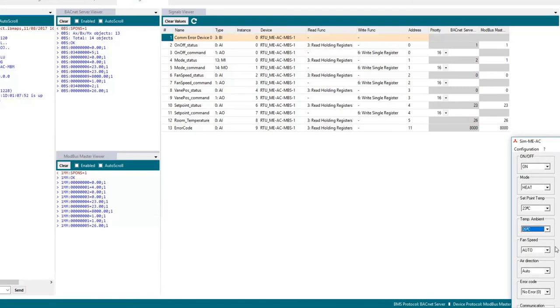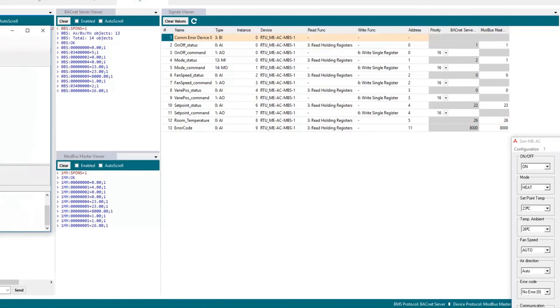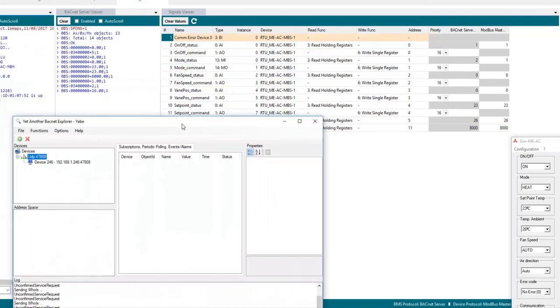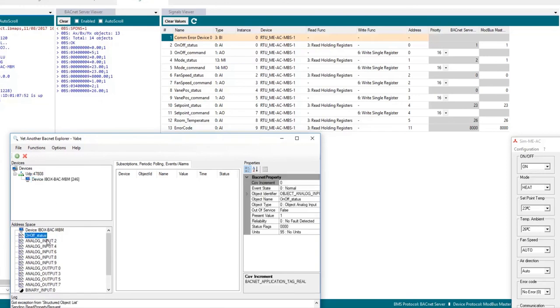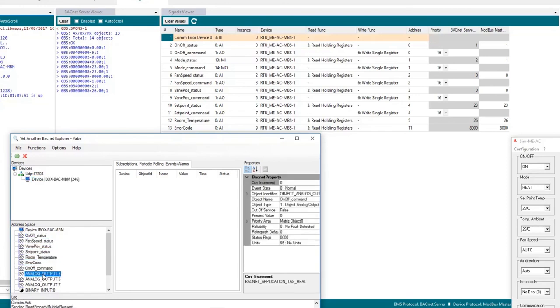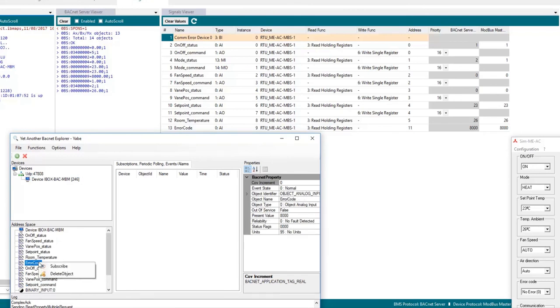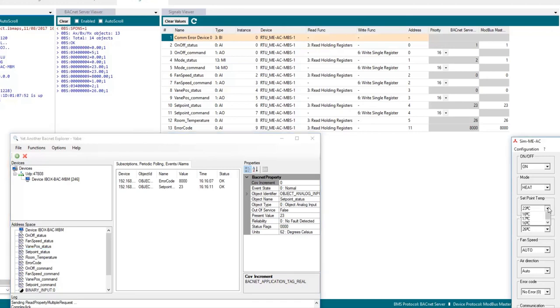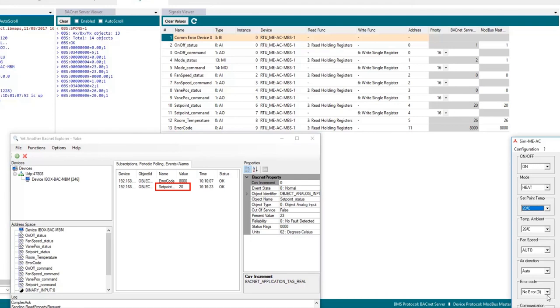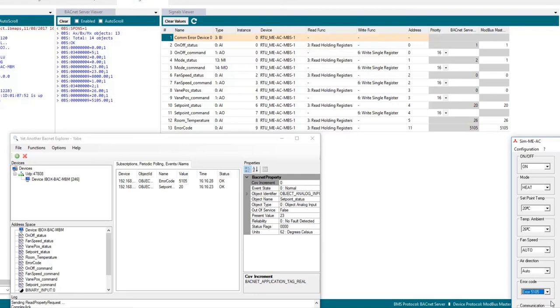Now let's use the BACnet client software. We will find our device by checking the IP and also we will see the signals available. That's okay. Now we will subscribe to a couple of signals for example error code and setpoint. And we will use our AC simulator in order to change these values. First the setpoint and it changes on the BACnet software and then we will simulate an AC error and also changes on the BACnet software.